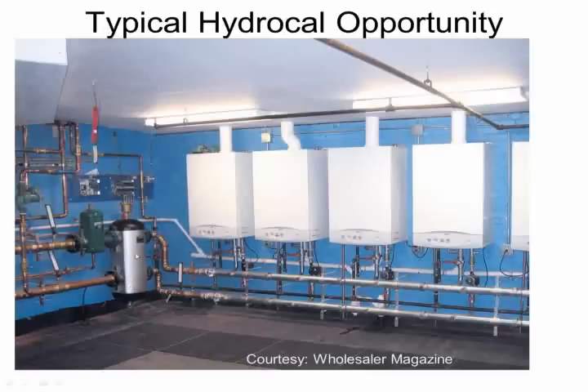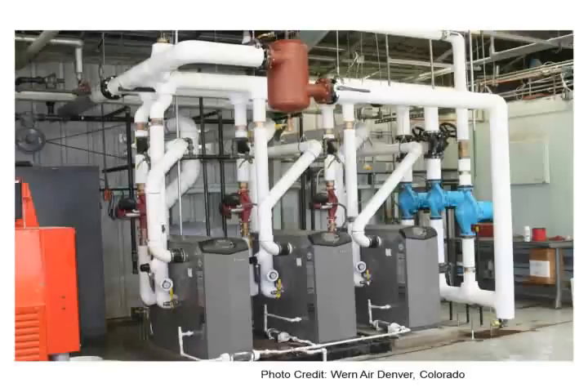So stepping back in time as an example, this system out in Maine had a hydraulic separator. This is before we had the 3-in-1 device, and that engineer wanted to have a dedicated air separator also added to it. He could have eliminated that device by using the 3-in-1 device.